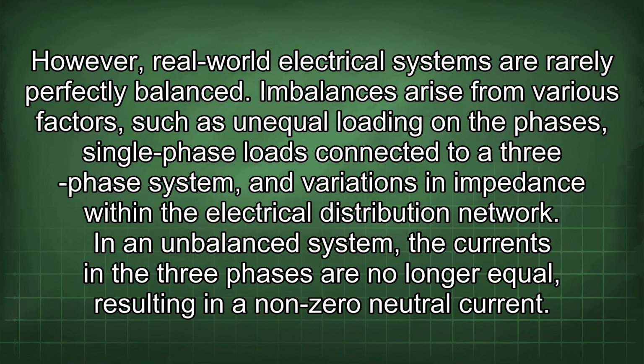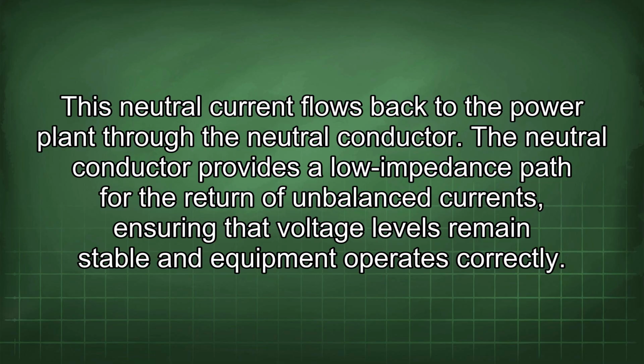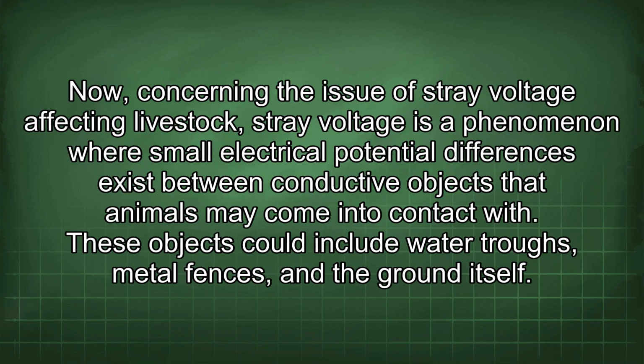Imbalances arise from various factors, such as unequal loading on the phases, single-phase loads connected to a three-phase system, and variations in impedance within the electrical distribution network. In an unbalanced system, the currents in the three phases are no longer equal, resulting in a non-zero neutral current. This neutral current flows back to the power plant through the neutral conductor. The neutral conductor provides a low impedance path for the return of unbalanced currents, ensuring that voltage levels remain stable and equipment operates correctly. Now, concerning the issue of stray voltage affecting livestock.